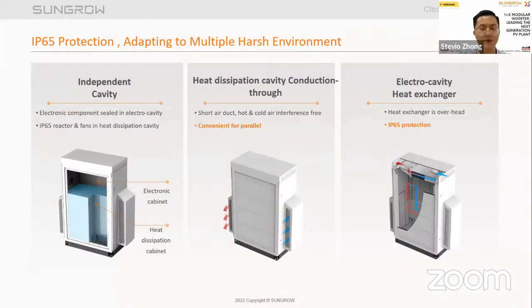IP65 protection enables 1+X to adapt to multiple harsh environments and is realized by the design of the cavity. See the first picture on the left. There are two cabinets designed in the cavity. One is a sealed electronic cabinet, and the other is for heat dissipation. With this kind of configuration, the electronic components will not be influenced by the heat in the unit. The reactor and the high protection fan in the heat dissipation cavity help to convect heat.